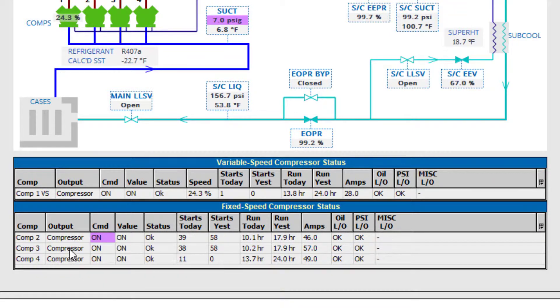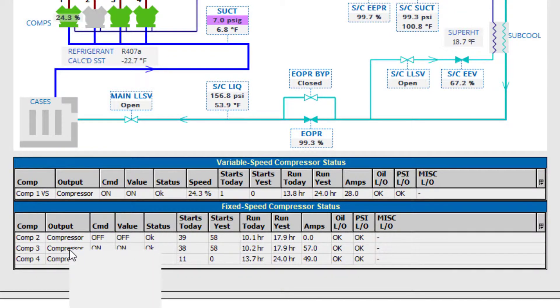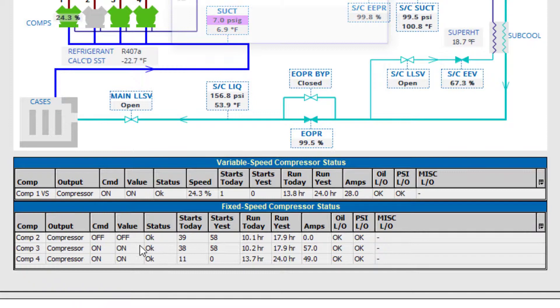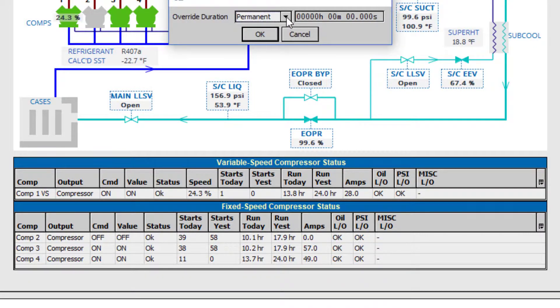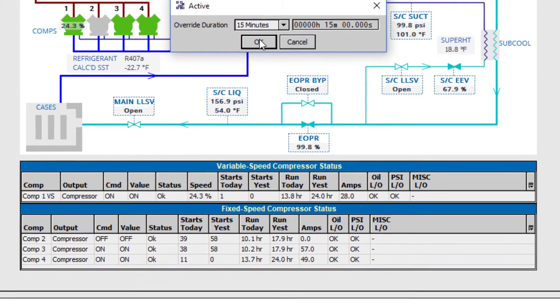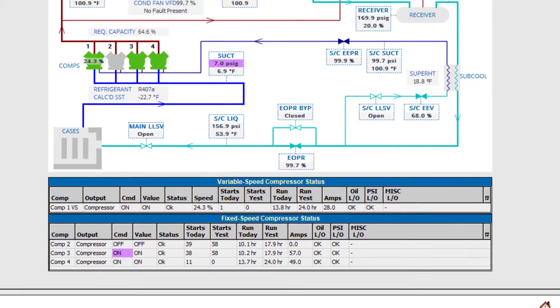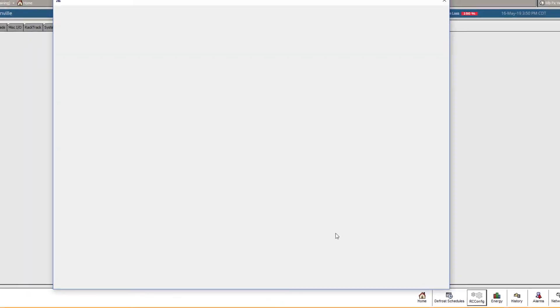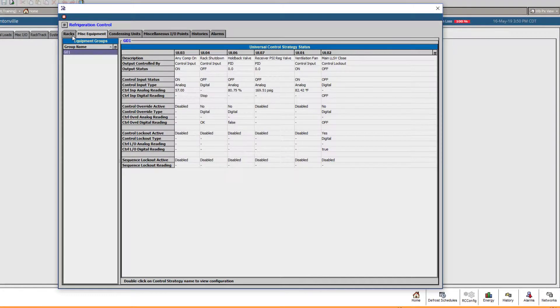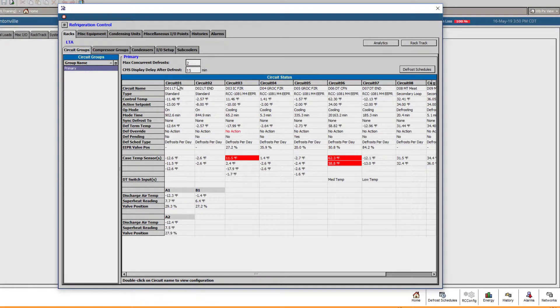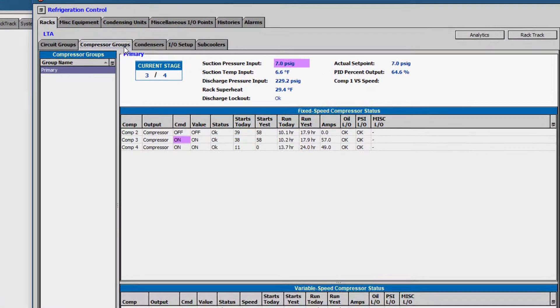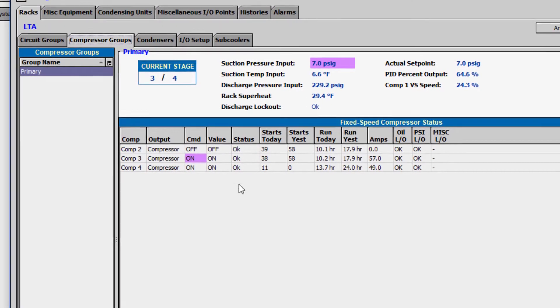When forcing a point here, notice the command highlights the point purple, alerting us that the point is forced. If we navigate to any other tab or page where this output is shown, it will appear in purple. These tabular points will also be highlighted if their corresponding graphical icon is overridden as well.